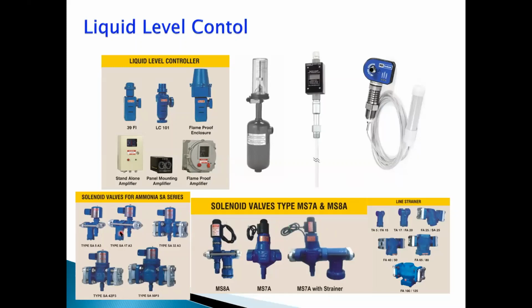Most of the time, the solenoid valves are fitted with filters or strainers, because the gap between the piston and the valve body is very, very small. So you do not want any foreign particles to come in and stop the operation. So it is normally provided with filters. It can be along with the valve, or it can be installed separately depending on the size of the plant. Please remember that ammonia and water are soluble, and there is no ammonia dryer like you have in Freon systems. So separation has to be done through the filters, strainers, only.